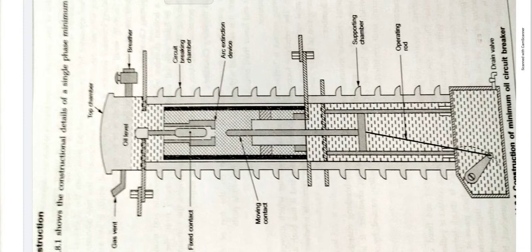Also, there may be some loss of dielectric strength of oil due to carbonization. This will reduce arc extinguishing capacity of the breaker. Thus, periodic checking of circuit breaker is essential after regular interval of 3 to 6 months.